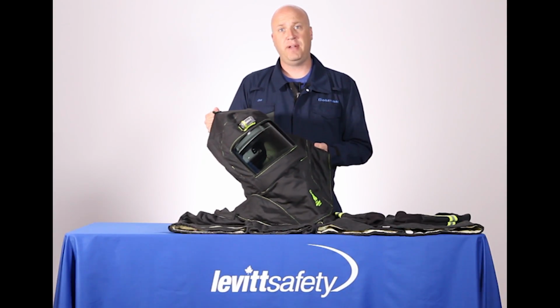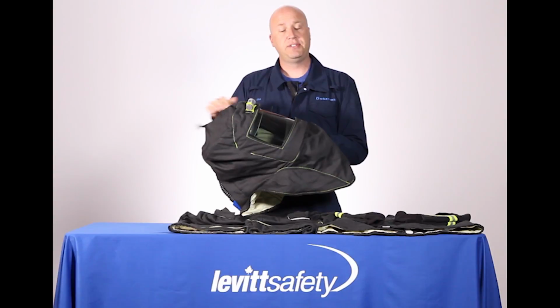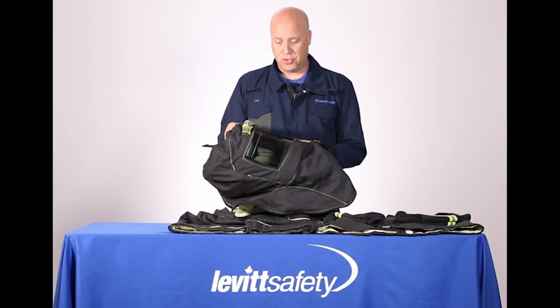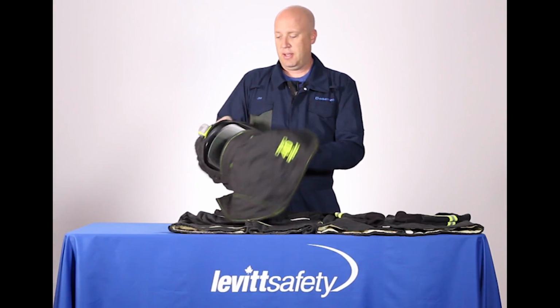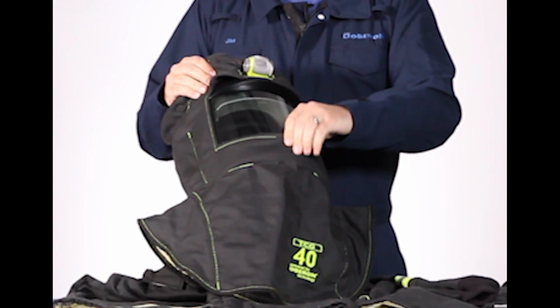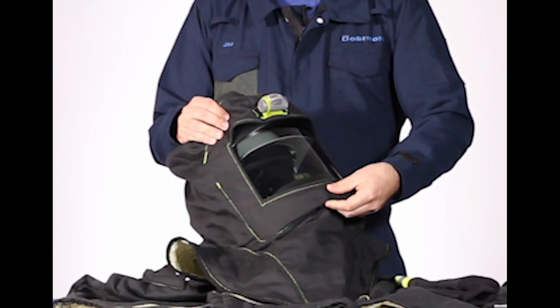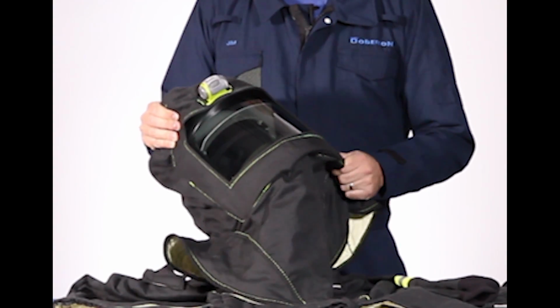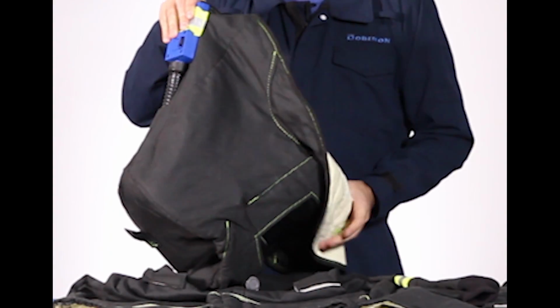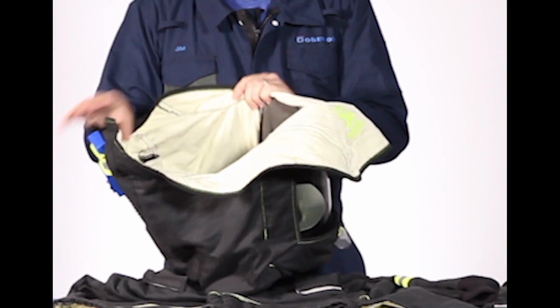When inspecting your arc flash suit hood, check the lens, make sure there's no excessive scratching, no cracks or other damage. The shield itself is held in by metal snaps. We want to make sure those snaps are closed before you proceed to use the hood. Checking the fabric on the outside as well as the inside for any damage or contamination.